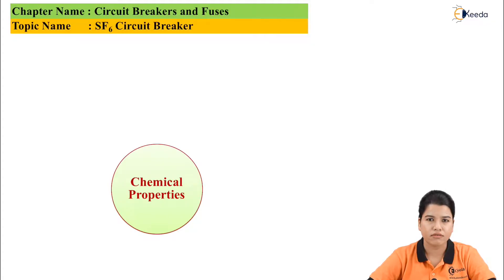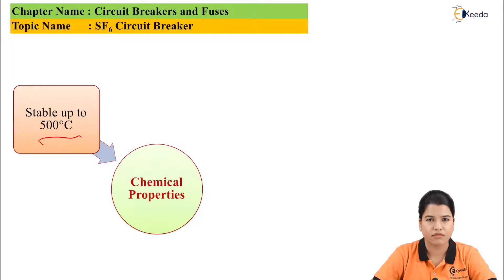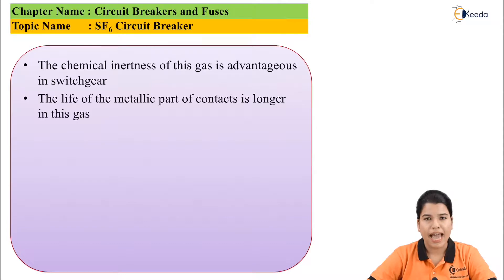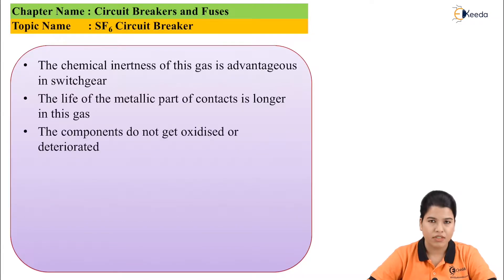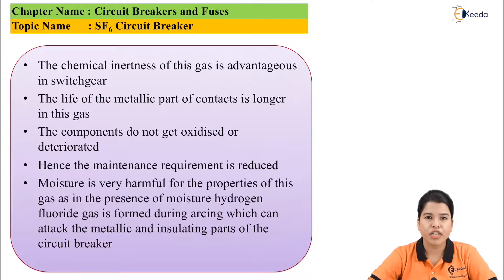Now let us see the chemical properties of SF6 gas. SF6 gas is highly stable up to a temperature of 500 degrees centigrade. It is also an inert gas, and its chemical inertness is very advantageous in switchgear applications. Because the gas is inert, the life of the metallic parts contained in the circuit breaker is very large and the components do not get oxidized. Due to all these properties, the maintenance required for the SF6 circuit breaker is very low. However, moisture if present is very harmful for SF6 gas, so the circuit breaker must be protected from moisture at all times.